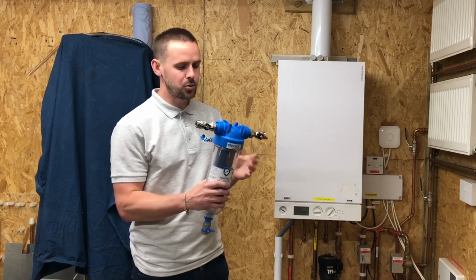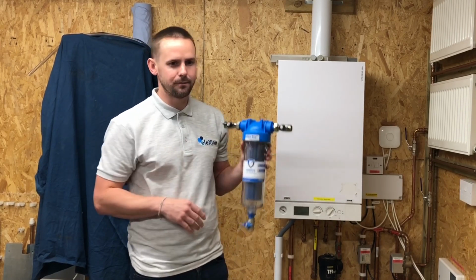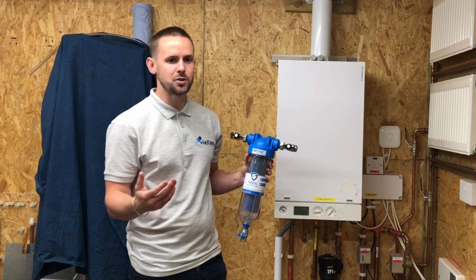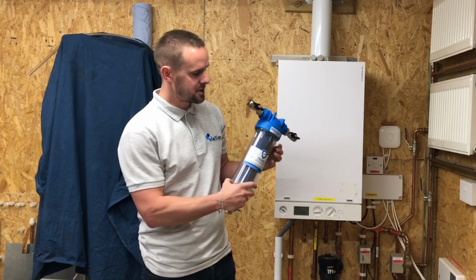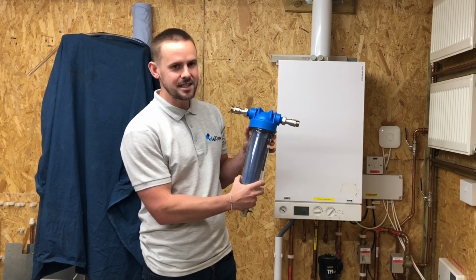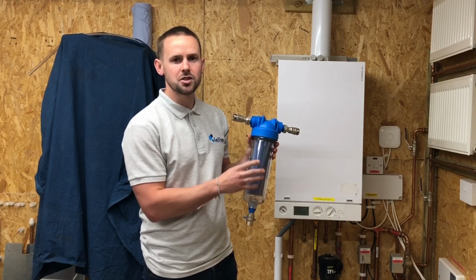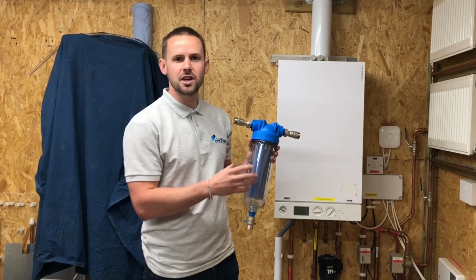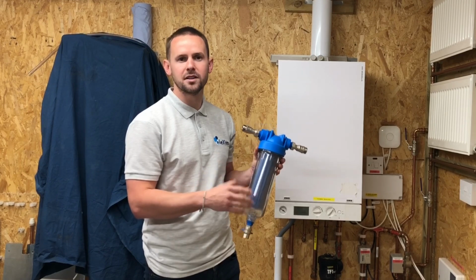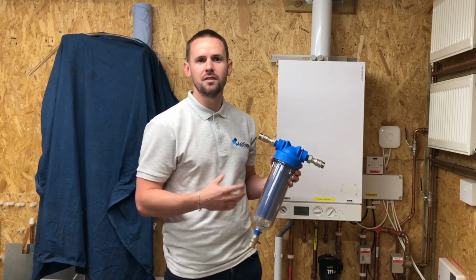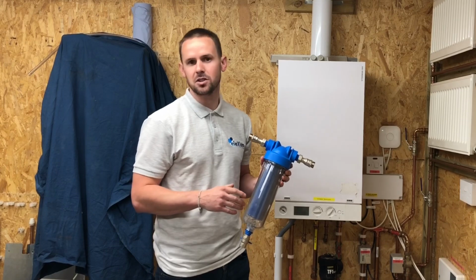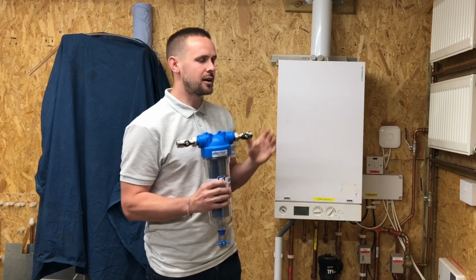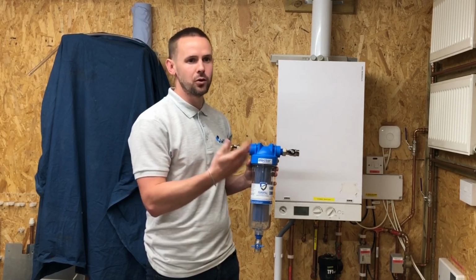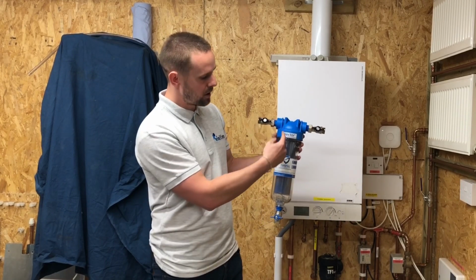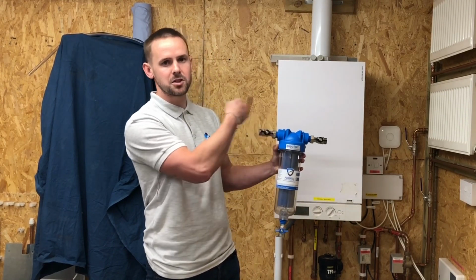It's a very simple device which has a little wall bracket, mounts on site, and you fill it in between the filling loop. There's a colour resin inside that's easy to monitor. It turns from blue to a yellow sandy colour. When it turns yellow sandy, we know the resin's expired. So it's something your customer can monitor very easily without any kind of test equipment. When the radiator comes off the wall and they go to refill the system, the water passes down through the resin and back out through the system, pre-treated and demineralised.